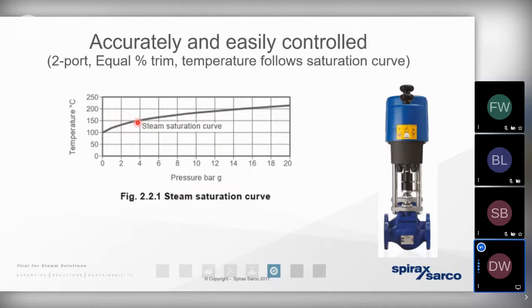So if you compare a steam heat exchanger to a water heat exchanger, we're likely to require a 3-port valve, and we're likely to require a small circulating pump on the skid to allow for that unwanted energy to move away from the process. So it can be a more complex situation or solution to engineer.